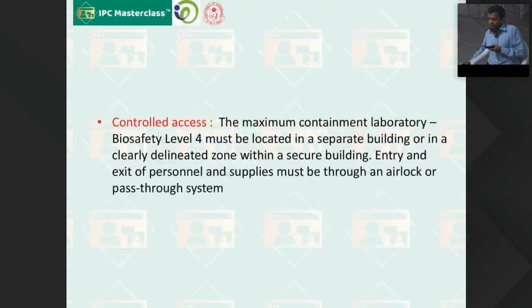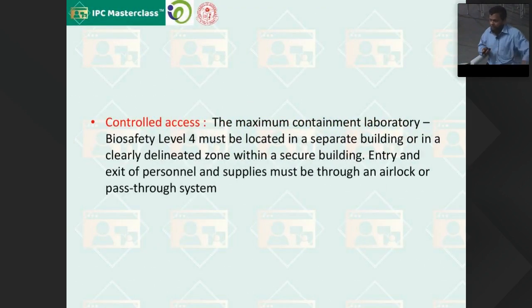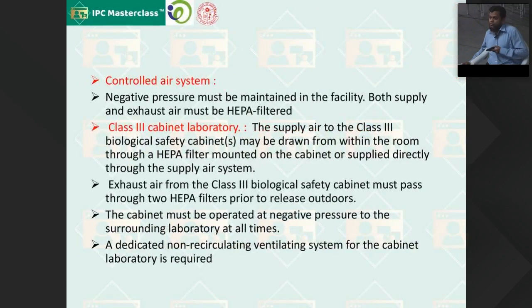If you see the next slide, controlled access is required for both, whether it is BSL-4 through the cabinet 3 or through the suit one, and a controlled air system is required for both. But the class 3 cabinet requires the air to be drawn from the room. It passes through the HEPA filters and directly through the system and is 100% exhausted. Exhaust air has to pass through 2 HEPA filters, and a dedicated non-recirculating ventilation system is required for the cabinet laboratory. So the BSL-4 class 3 cabinet laboratory requires a class 3 biosafety cabinet.